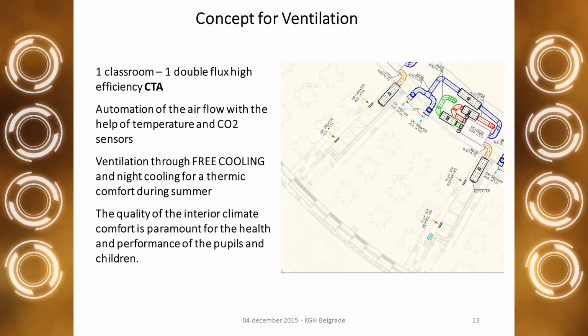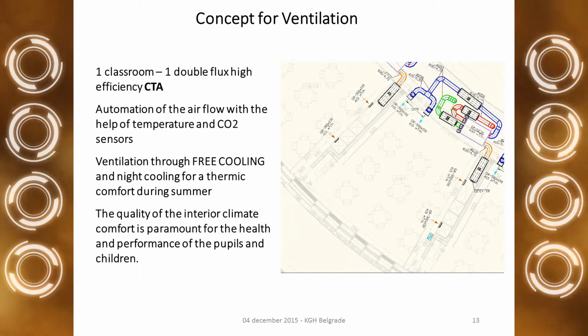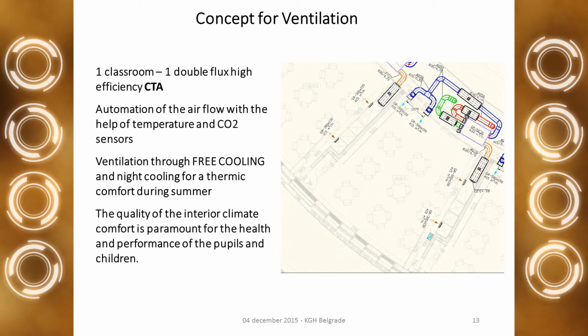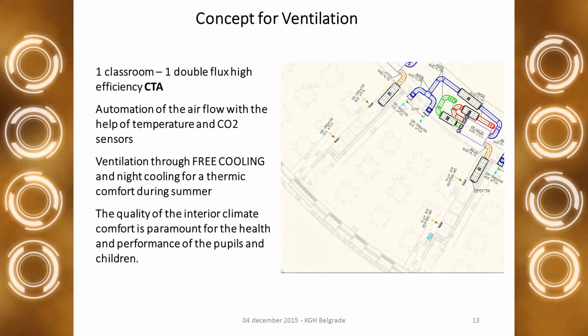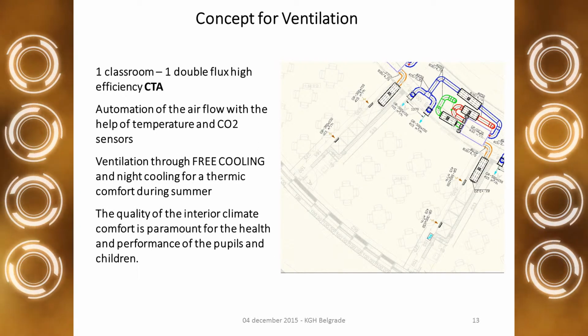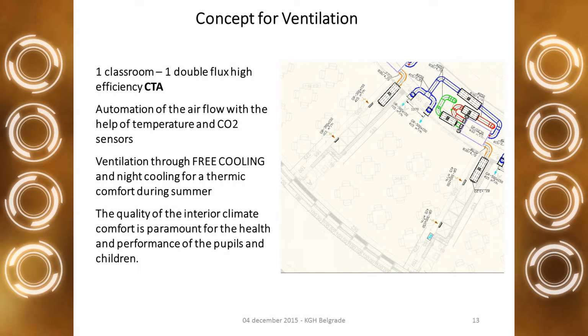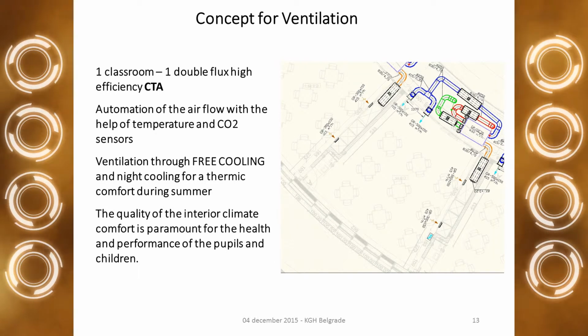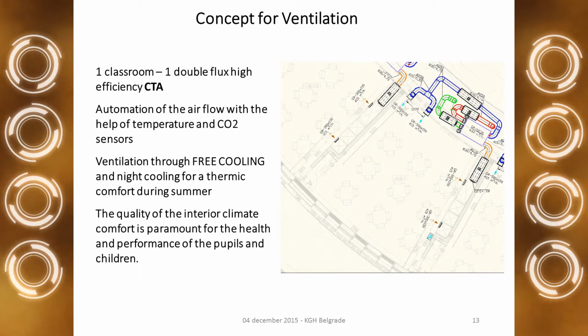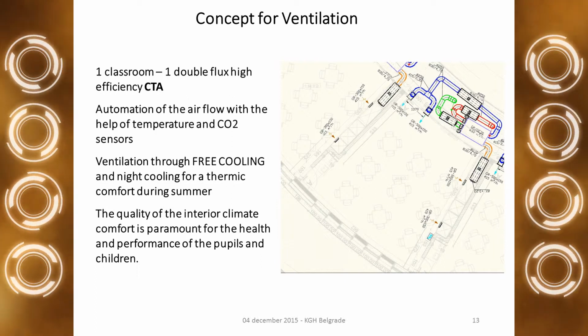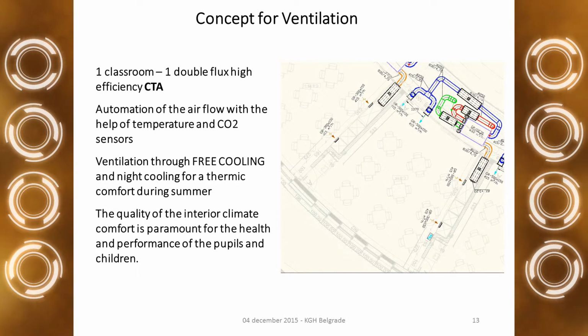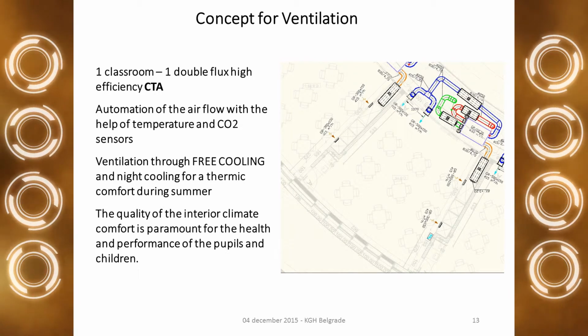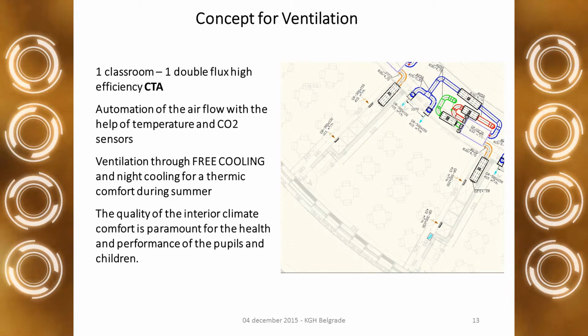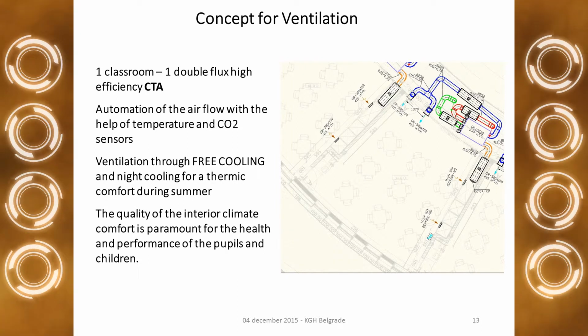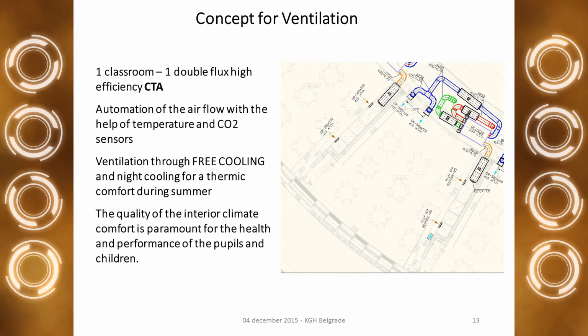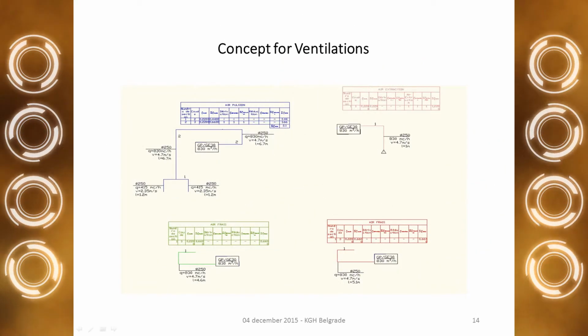The concept for the ventilation: a double flux high efficiency air handling unit for each classroom, automation of the airflow with the help of temperature and CO2 sensors, ventilation through free cooling and night cooling for thermal comfort during summer. The quality of the interior climate comfort is paramount for the health and the performance of the pupils and children.